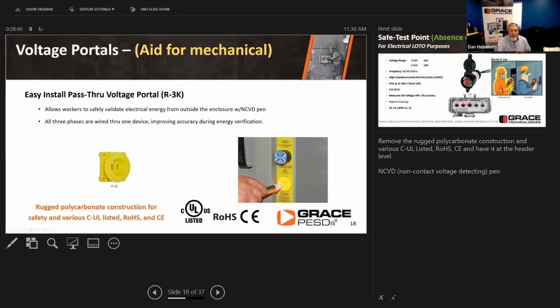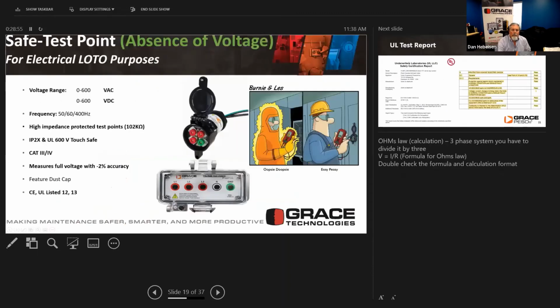This gives you that opportunity because we create an environment where you can measure it at the point of use and just verify, again, for a task qualified person, not an electrically qualified person. For the electrically qualified person, we take the hazard of doing the lockout tagout, we bring it to the outside of the cabinet, and we take that measurement at a test point that's actually mounted on the cabinet. And it doesn't matter the frequency that it's being provided, whether it's 50 hertz, 60 hertz, or all the way up to 400 hertz. This is being utilized on the output side of some variable frequency drives, and still gives you the opportunity to measure that the voltage is no longer present.